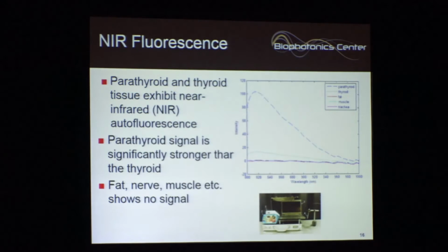So we decided, well, let's go see in patients. Like I said, we have relatively easy access to doing clinical work. So we took the system. It's a portable system, as you can see, of what we build and use. It's very small, briefcase size. The laser is the blue box in there. The detector is that little box, and everything is computer controlled. So we said, let's go from the lab to the clinic, get patient consent, and see what we get when we look at thyroid and parathyroid.